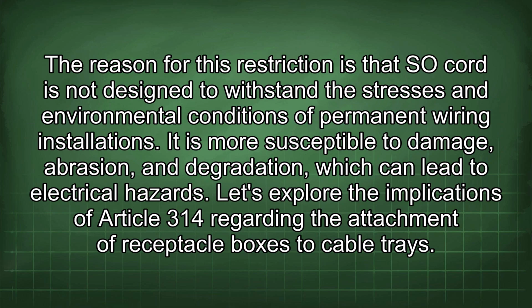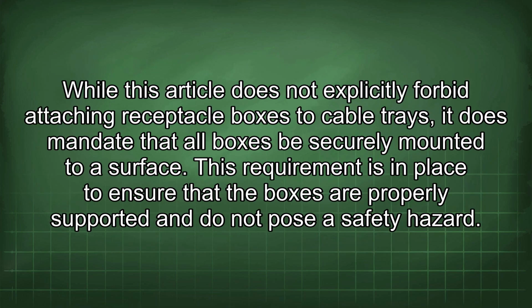The reason for this restriction is that SO cord is not designed to withstand the stresses and environmental conditions of permanent wiring installations. It is more susceptible to damage, abrasion, and degradation, which can lead to electrical hazards. Let's explore the implications of Article 314 regarding the attachment of receptacle boxes to cable trays. While this article does not explicitly forbid attaching receptacle boxes to cable trays, it does mandate that all boxes be securely mounted to a surface. This requirement is in place to ensure that the boxes are properly supported and do not pose a safety hazard.